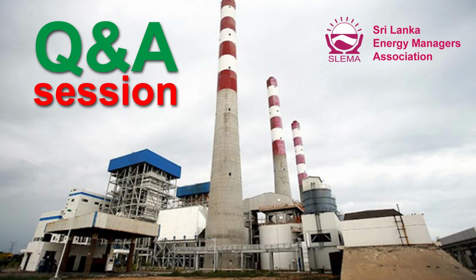So, of course, the final decision will be made in the coming weeks as to what the auxiliary power source will be. But definitely there will be an auxiliary power source adequate to keep the minimum auxiliaries in operation, until the grid comes back, or to take the power plant to a safe shutdown, so that when the grid comes back, it can be brought back in 4, 5, 6, 7 hours, depending on the stage it is at when the grid is restored.